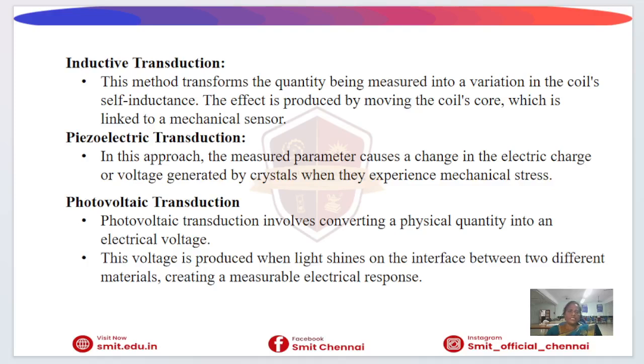Inductive transduction converts the measured quantity into a change in inductance. This is achieved by moving a magnetic core inside a coil, causing changes in self-inductance. An example is the LVDT, used for displacement measurement. Piezoelectric transduction generates electrical charge when mechanical stress is applied to certain crystals. These transducers are widely used for dynamic pressure and vibration measurements.